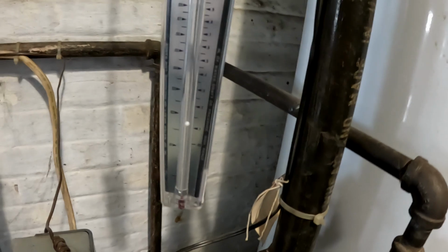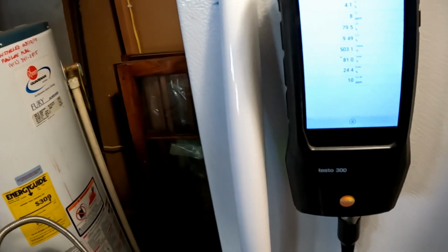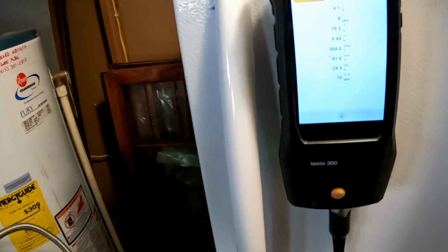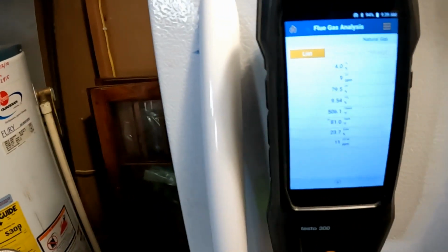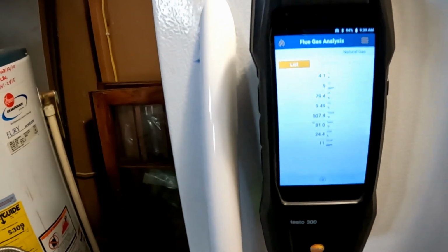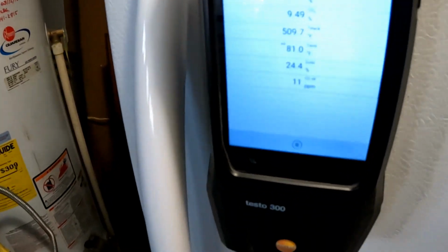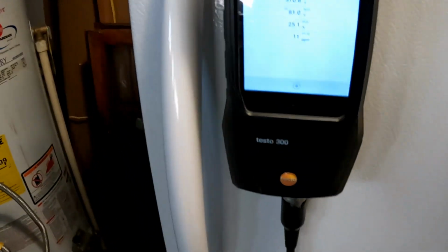It's below 2. You know, 1, it's not climbing. Now this test will show not only rising CO, but lowering oxygen levels, meaning the air going into the boiler itself and the draft to it. So this oxygen will deplete more.